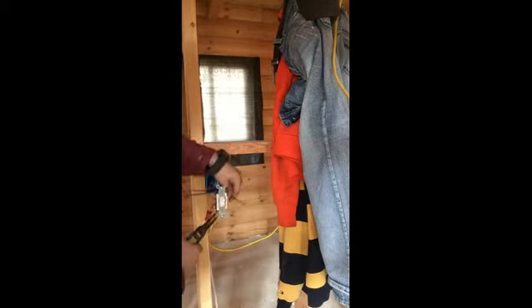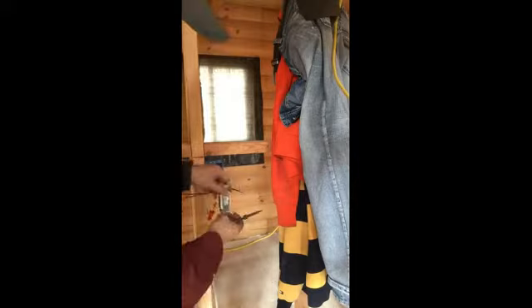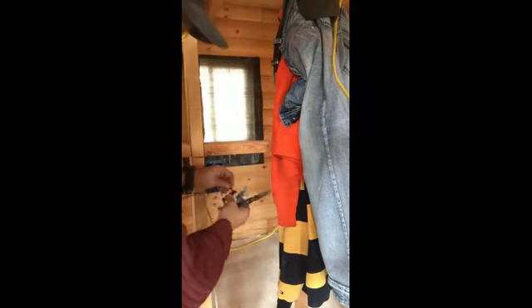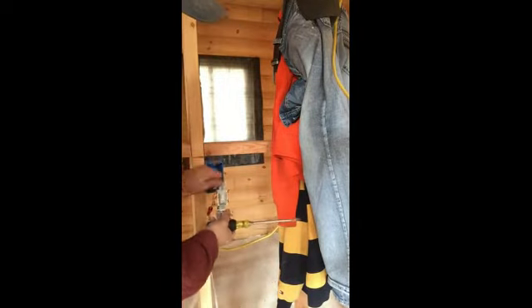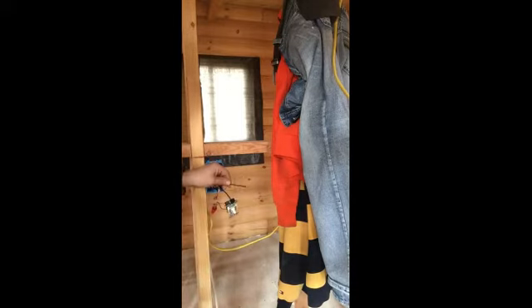Step 6, wiring switches. For switches, you'll want to connect the grounding wire first, which is the bare wire once again. But first you'll have to connect two bare wires together with a third six-inch piece of bare wire that you would cut off from an unused piece of 12-2 wire that you already have laying around the house. The reason for this is that the switch and the light and the power grounding wire all have to be connected. So that's a three-way connection right there. The same thing goes with the neutrals. All three will be connected once again and pushed back behind the switch box, because you have to make room for the switch.